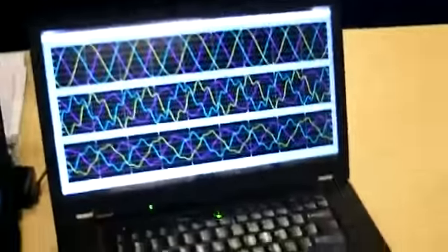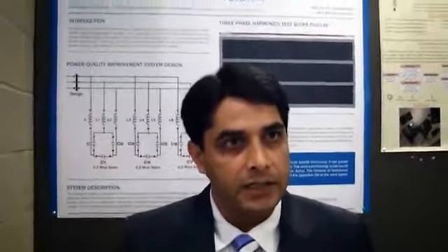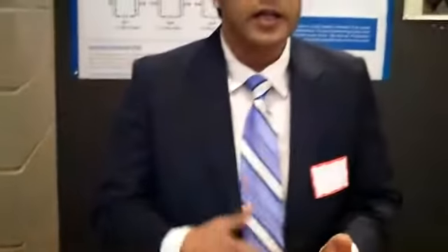Yeah. So that's why we need a solution to improve the power factor and remove the harmonics. That's our objective, to improve the wind tunnel at ACE building, Automotive Center of Excellence. You said a lot of reactive power is wasted. Yeah, so when we improve the power factor, then reactive power goes to real work, right? Yes. So that's basically our problem. So we are designing a capacitor bank in order to do that.